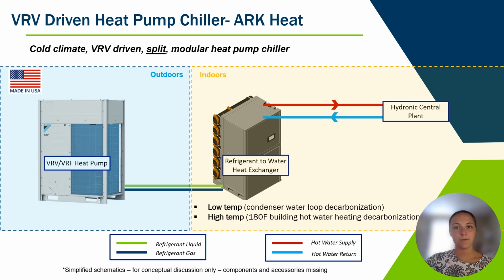We then also have the option to include a modular headered water-to-water heat pump after these XE units, and that's what we call the boost unit. And this can be used to boost the water temperature to deliver high temp water at 180 F, which allows us to utilize existing high temperature building hot water heating infrastructure.